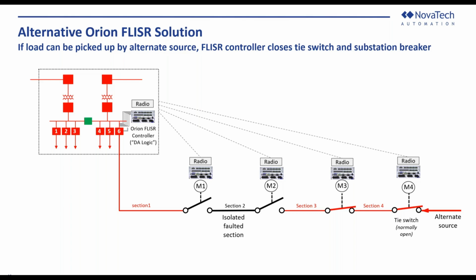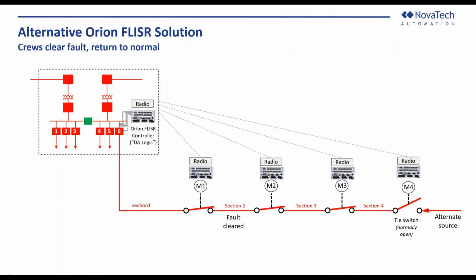Once the isolated fault section is there, the crew will then go out and repair the line over there, and then clear the fault and return to normal operation. The tie switch at M4 will be open, and it's back to normal. This is a very simple example of a FLISR scheme. However, there might be different topologies that you may have, and we would be more than happy to work with you to work on a FLISR scheme for your distribution automation scheme.